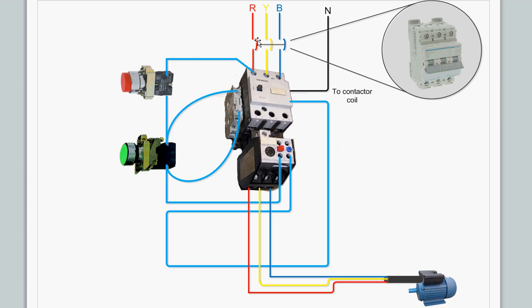This circuit breaker—people can use a fuse or this circuit breaker here. In this case, the contactor coil is 220 volt. Basically, you get the power here, it goes to the stop button, and then it goes to the start button, and it goes to this overload protection. This is normally closed contact, so it goes here, goes this way, and then goes to the contactor coil. Neutral comes directly to the contactor coil. So initially, when the person presses the start button, it closes the complete circuit.